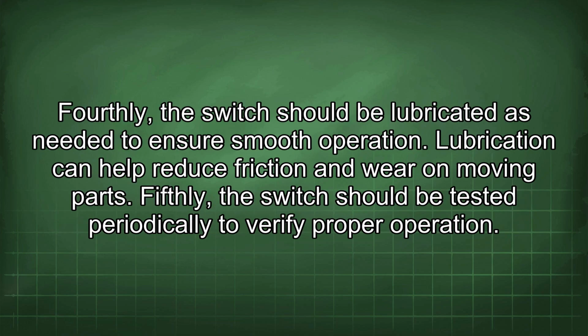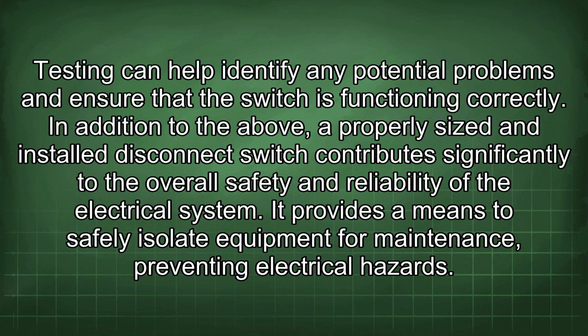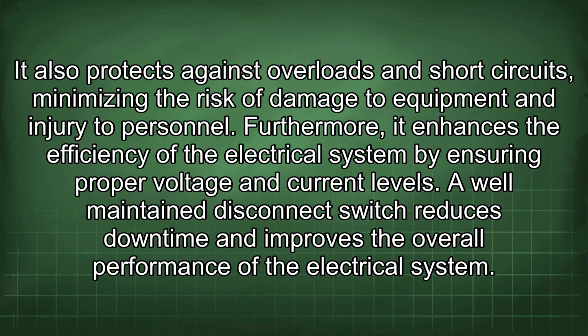Fourthly, the switch should be lubricated as needed to ensure smooth operation. Lubrication can help reduce friction and wear on moving parts. Fifthly, the switch should be tested periodically to verify proper operation. Testing can help identify any potential problems and ensure that the switch is functioning correctly. In addition to the above, a properly sized and installed disconnect switch contributes significantly to the overall safety and reliability of the electrical system. It provides a means to safely isolate equipment for maintenance, preventing electrical hazards. It also protects against overloads and short circuits, minimizing the risk of damage to equipment and injury to personnel.